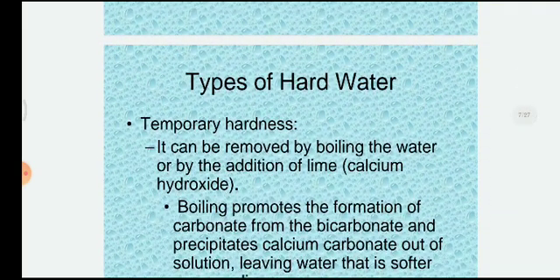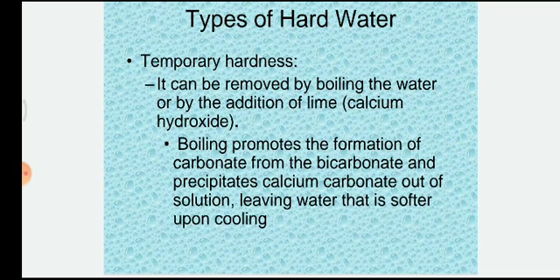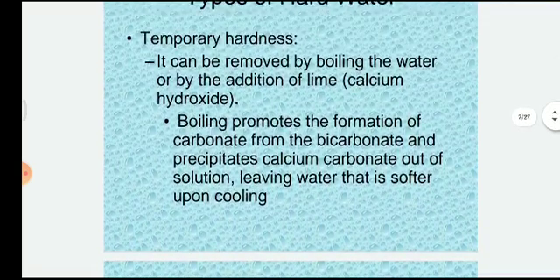Temporary hardness can be removed by boiling the water or by the addition of lime — calcium hydroxide. Boiling promotes the formation of carbonate from bicarbonate and precipitates calcium carbonate out of solution, leaving softer water upon cooling.